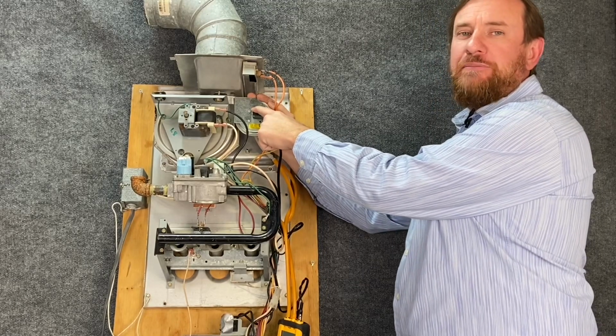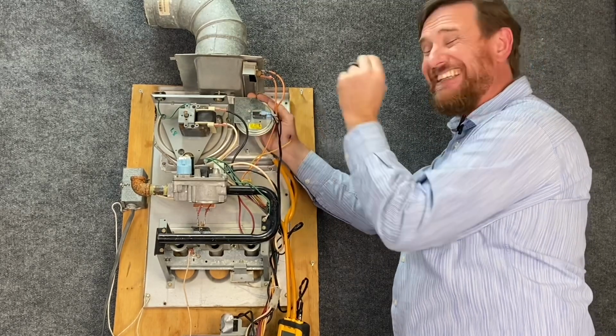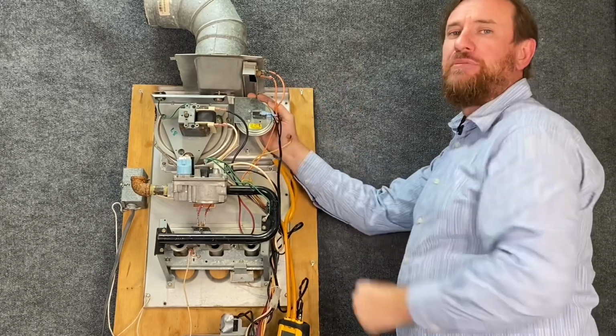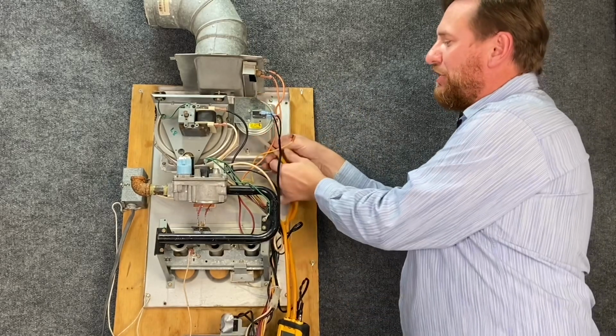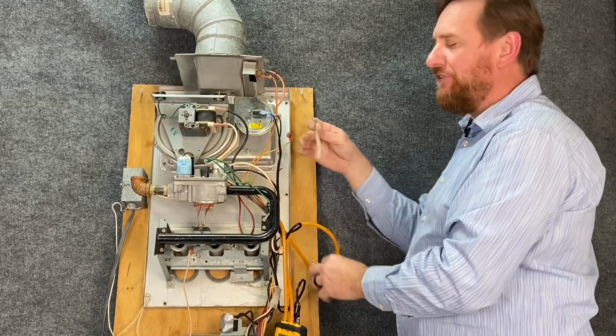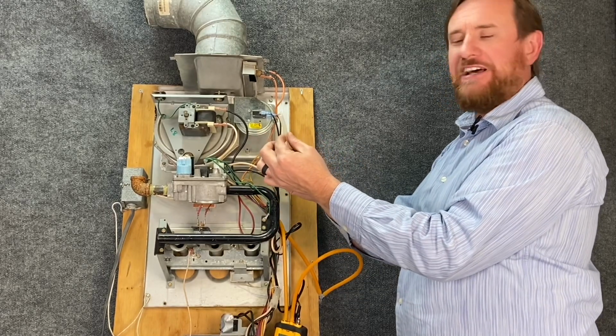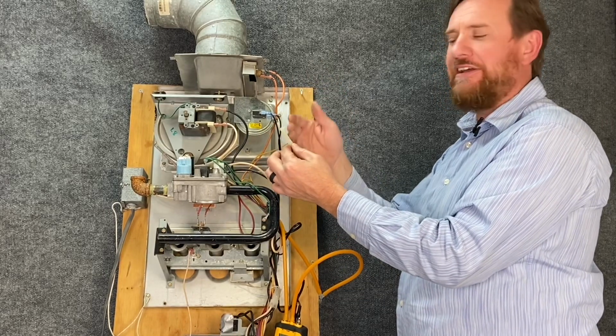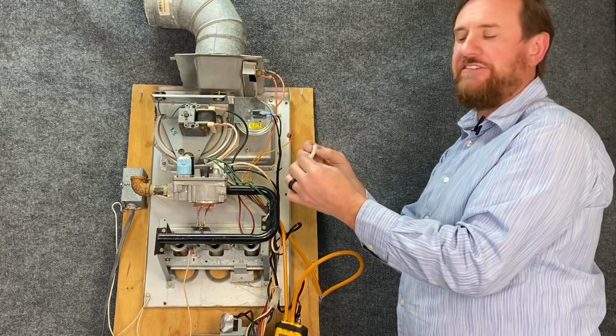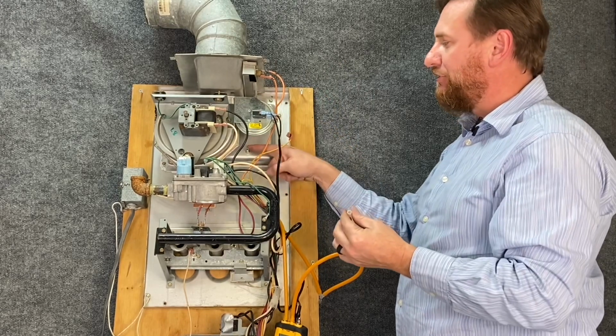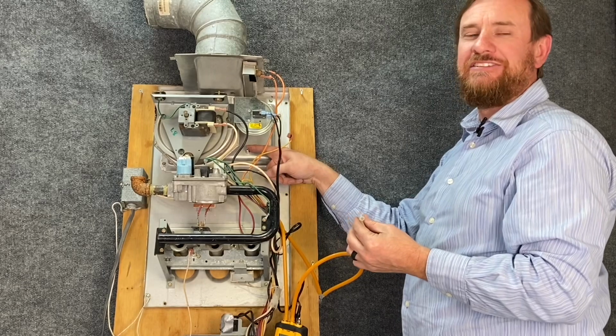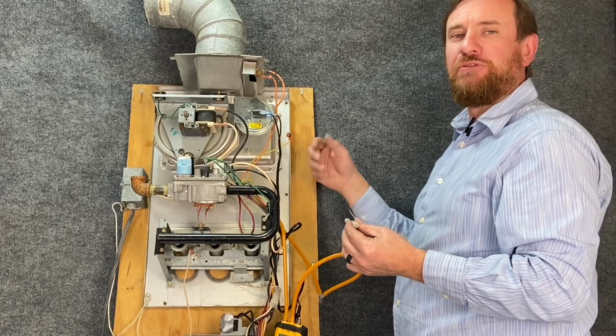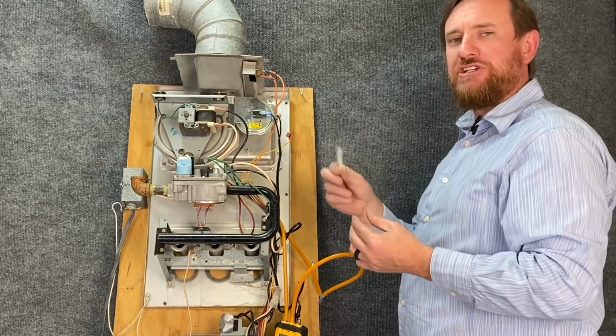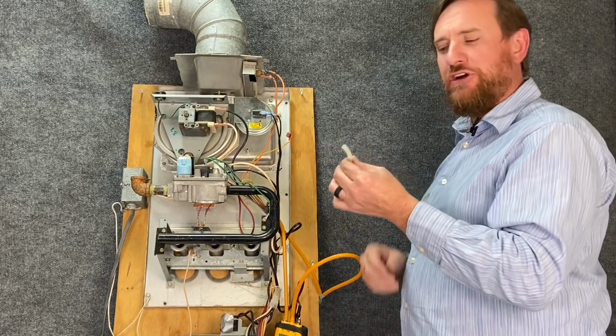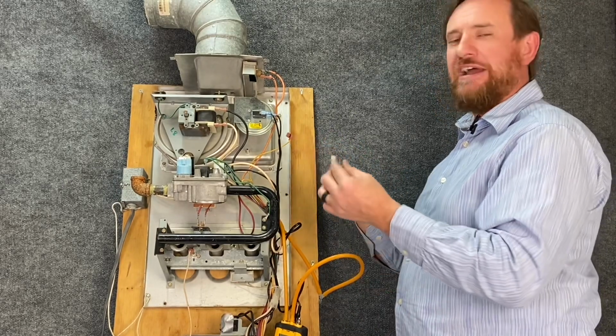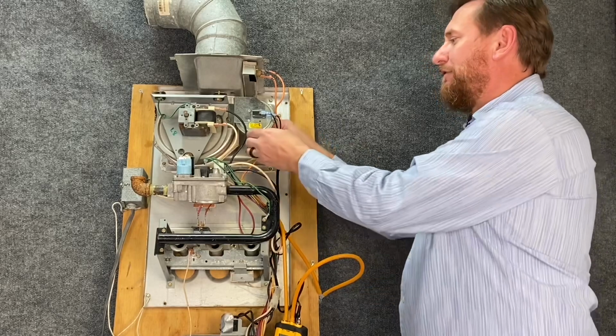This one closes at 0.25. I want to make sure without a doubt that my new one closes at 0.25. The other thing you want to check is these hoses. The hoses that connect it become brittle over time. They can be cracked, they can pull air in, and that air can make the switch not get a good seal. So you want to check this, and also sometimes this little tube where it connects into this inducer draft can clog up with rust or other contaminants. So you want to make sure that's in good shape. I used to keep extra hoses with me just in case they cracked or broke. I can replace them and not have to worry about it.